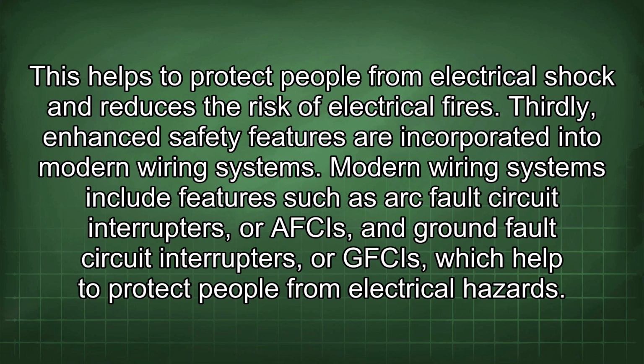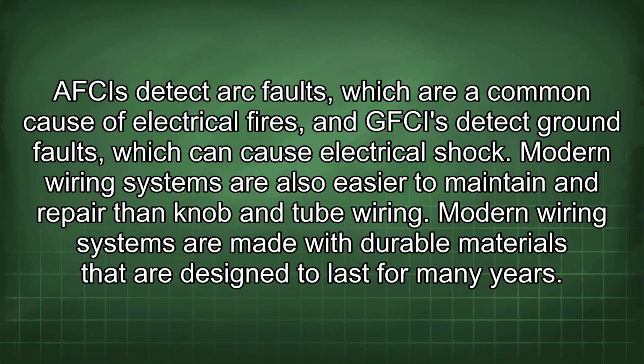Thirdly, enhanced safety features are incorporated into modern wiring systems. Modern wiring systems include features such as arc fault circuit interrupters, or AFCIs, and ground fault circuit interrupters, or GFCIs, which help to protect people from electrical hazards. AFCIs detect arc faults, which are a common cause of electrical fires, and GFCIs detect ground faults, which can cause electrical shock.